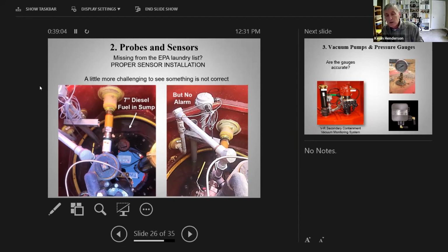The service guy got called out. He went out. I guess he didn't feel like getting wet that day. He didn't want to fool with trying to fix the union that was leaking. So all he did was take the communication cable, the wire, and just wrap it around the electrical conduits so that he could pick up the sensor within that pipe high enough to get it out of the fuel and get it out of alarm. So sometimes you got to look a little closer. Sometimes it's not so obvious. You've got to make sure that that sensor is in fact sitting at the bottom of the sump.